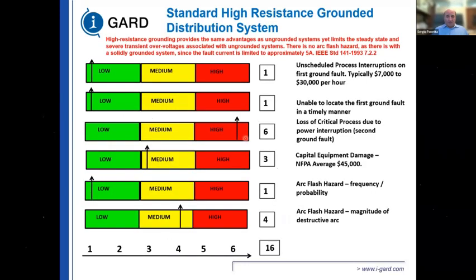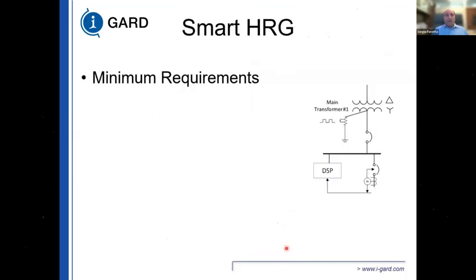So with a standard HRG system, your unscheduled process interruption is 1, their ability to locate the ground fault is 1, loss of critical process due to a second fault is high because you can't detect that second fault. Capital equipment damage is medium, frequency is low, arc flash hazard when a second ground fault occurs is medium. So you're at 16.